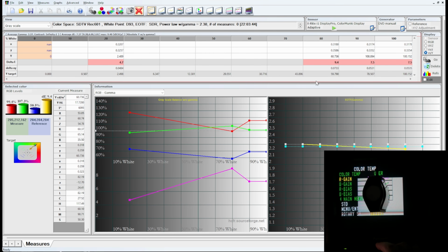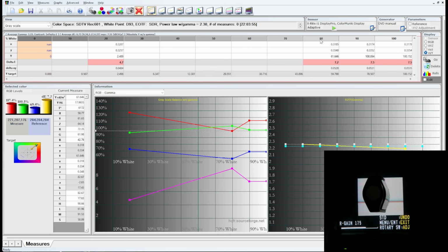So I have my red gain, blue gain, bias down here. Gain, remember, is for the high end, so right now, if I'm looking at this 80 IRE pattern, well, let me get out of the menu because we want to do an accurate scan. You can see it's telling me I have way too much red. Remember, we're trying to match whatever number this green one says. This green one may not always say 100%, but as you get these numbers closer, everything will start to say 100%. So let me just show you how that works.